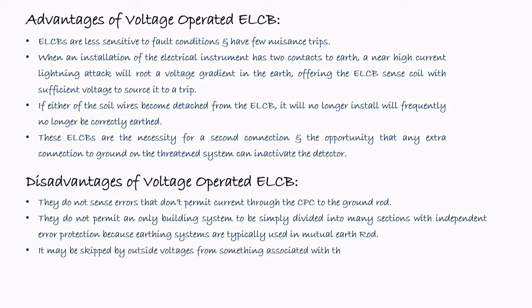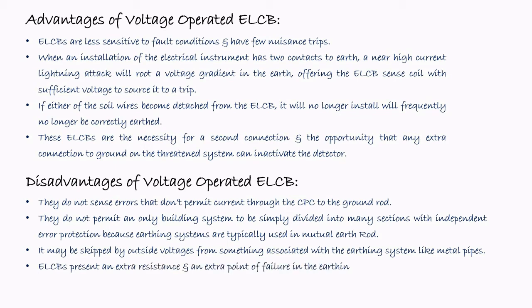It may be tripped by outside voltages from things sometimes associated with the earthing system, like metal pipes. ELCBs present an extra resistance and an extra point of failure in the earthing system. So these are some advantages and disadvantages of the voltage controlled ELCB.